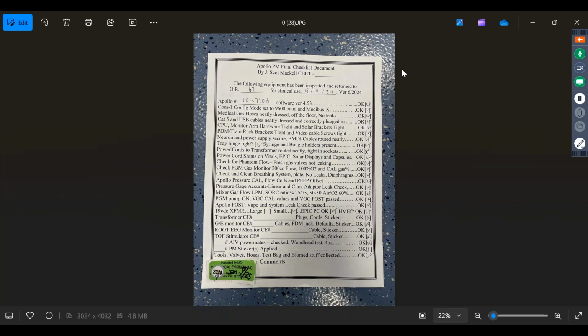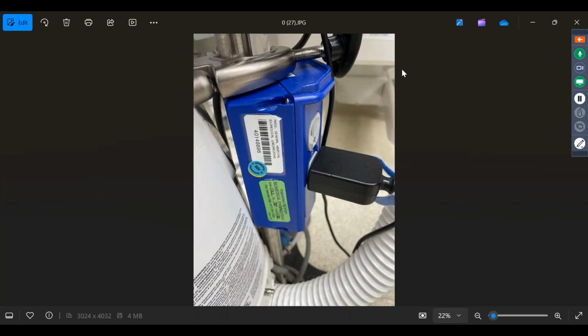Then you do your pressure gauge. So you've got your pressure cal, your flow cells, your PEEP offset. Those are pages in the service menu. Pressure gauge, accurate and linear. So I use a magnehelic gauge for that. I take the breathing bag off, put the magnehelic gauge right on there. And, you know, I like it because it's big and the numbers are big on it. My eyes like big numbers because I'm of that age. And you can pressurize the anesthesia machine and you'll see the, oh look, the O2 flush button doesn't work because I only have an air cylinder on.